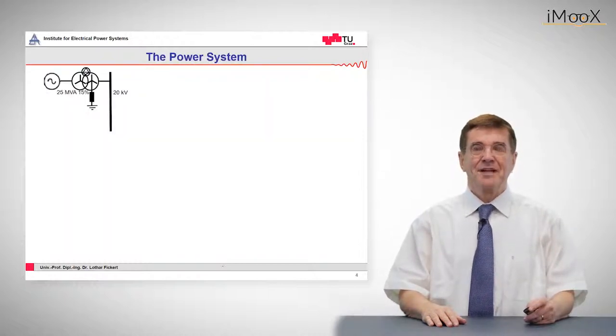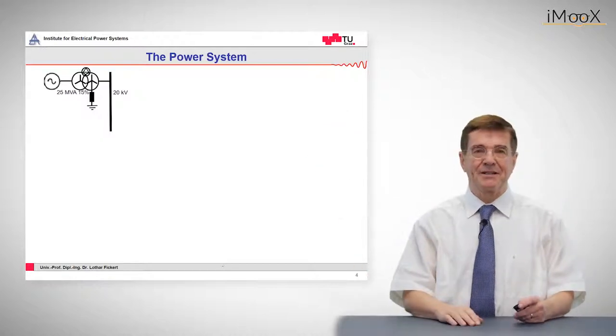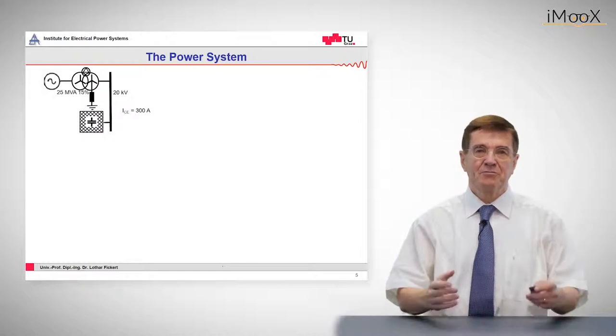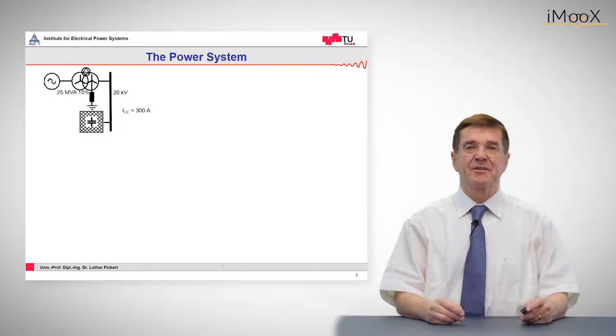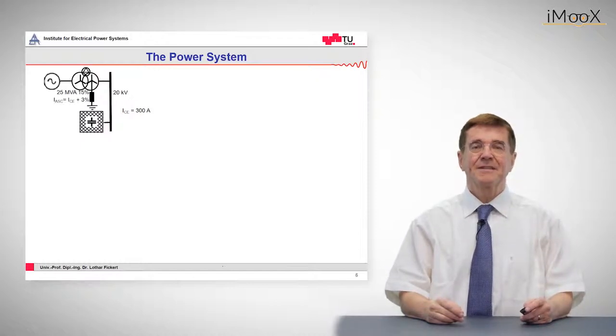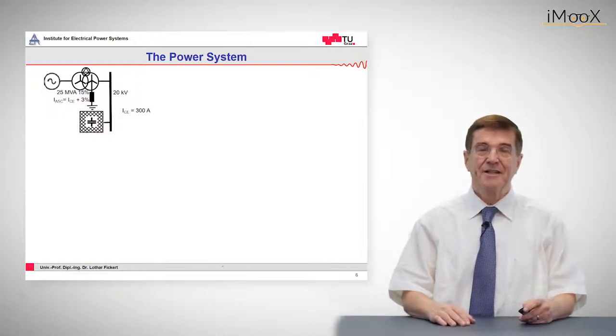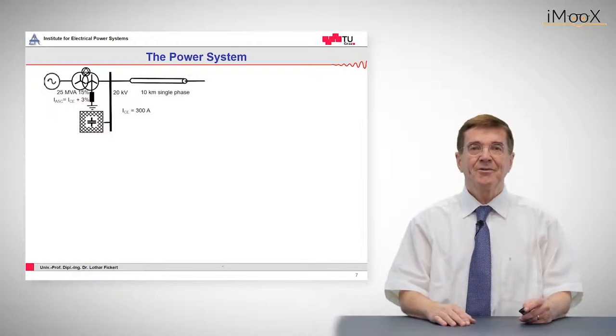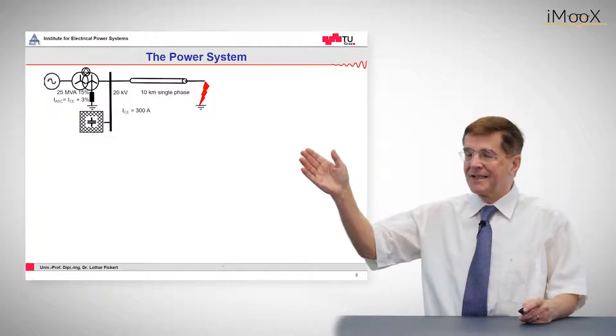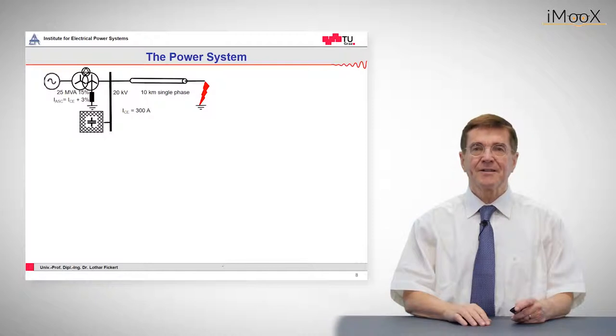I will give you an example of a medium voltage network which consists of a transformer feeding into a 20 kV busbar. Then there is a grid, let's imagine it is a cable grid connected to it with a capacitive earth fault current of 300 amps, and we set the arc suppression coil to 3% overcompensated, so the nominal current of this arc suppression coil is 309 amps. Now there is one faulty line which consists of 10 kilometers of three single phase cables, and at the end we have a short circuit.